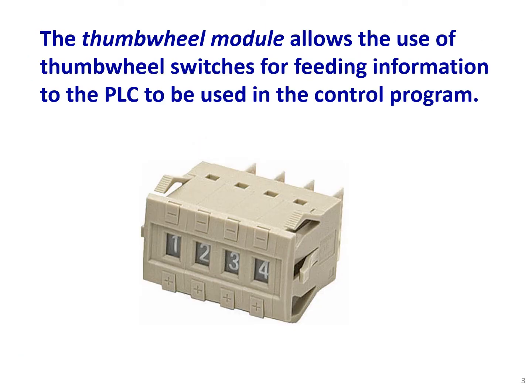The thumb wheel module allows the use of thumb wheel switches for feeding information to the PLC to be used in the control program. It's another type of special input that needs a special module. It's a digital thumb wheel, and we can assign a number and send it to the PLC program. This number could be a preset value — for example, for a water tank — and the operator can change that. This type of input device needs a special module.